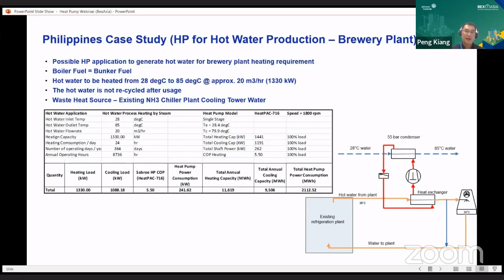So again, we have a waste heat source in this plant, which in this case is a cooling tower plant. So we extract from the cooling tower water, cooling it from about 36 to about 30 degrees C, from which we can generate hot water from 28 to about 85 degrees C. So the same reasoning again, choosing a heat pump with a very high COP of 5.5 on the heating side and the electric power it consumes. So we again do a very parallel kind of study between a boiler fuel consumption doing the same heating process versus that of an electrical heat pump.